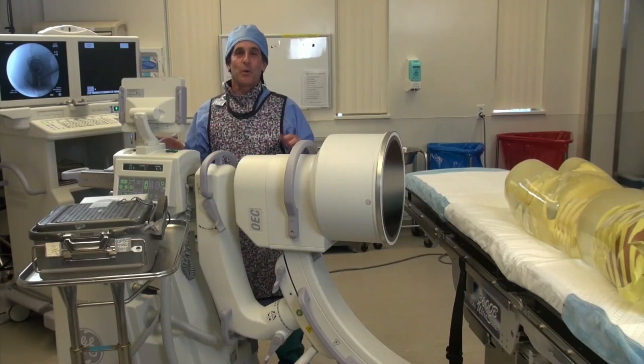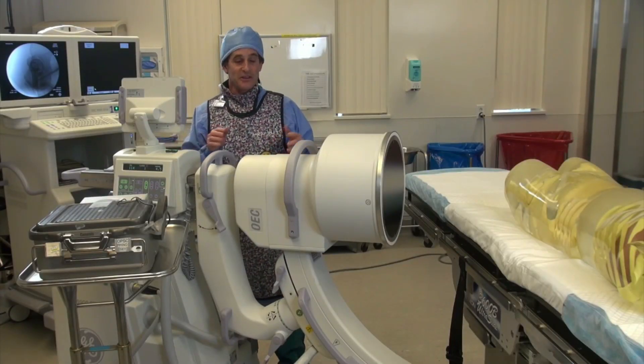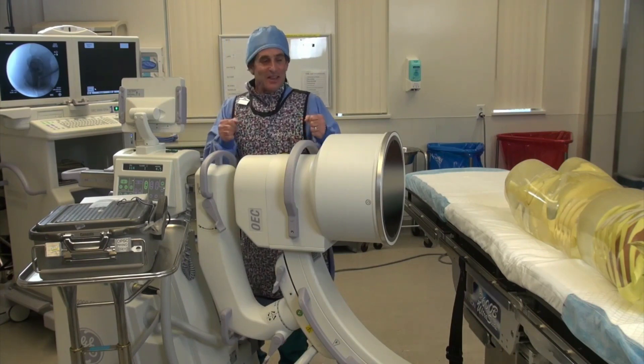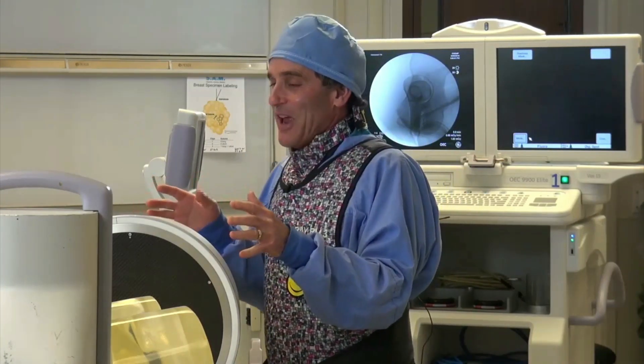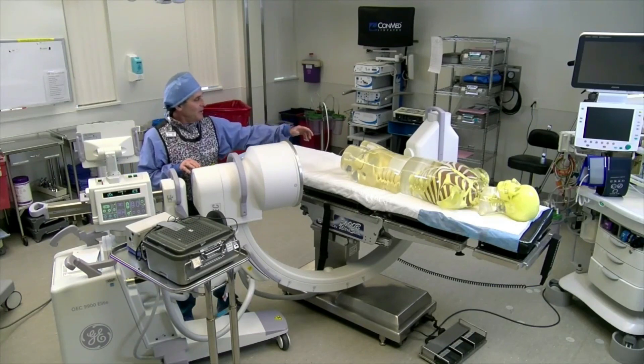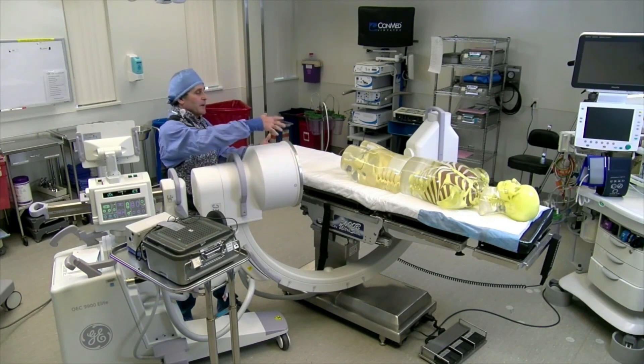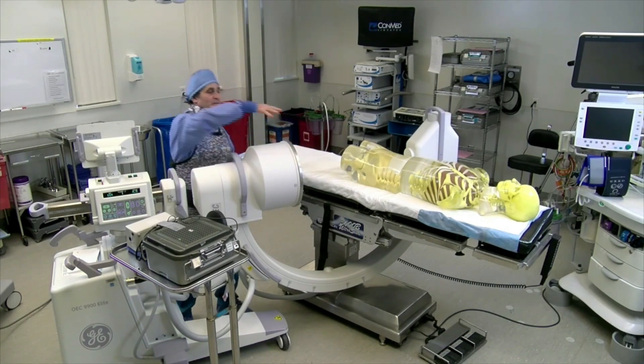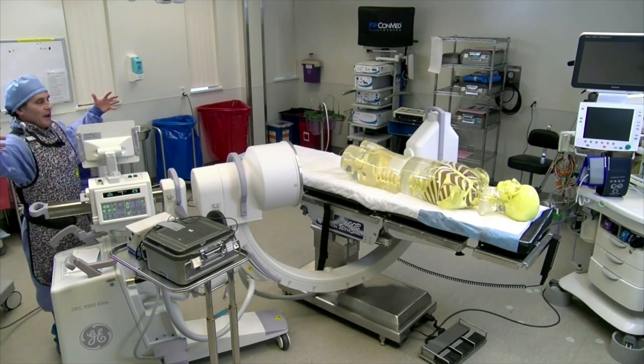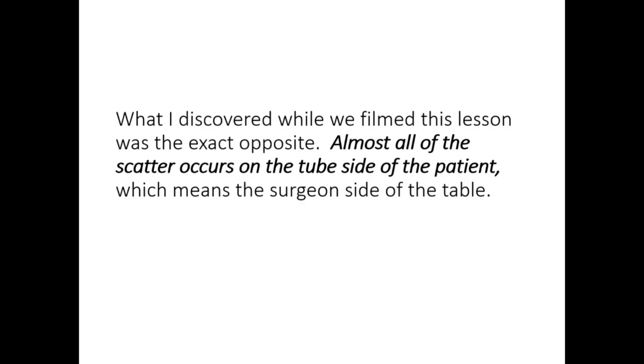I have been a tech for well over 35 years, and it really wasn't until we did this scene that I found out I was wrong the whole time about where scatter is happening. I always figured x-rays come out, hit the patient, go through the patient, come over to your side, and because it's scattered it's bigger and creates this whole area of radiation everywhere. What I discovered while we filmed this lesson was the exact opposite — almost all of the scatter occurs on the tube side of the patient, which means the surgeon's side of the table.